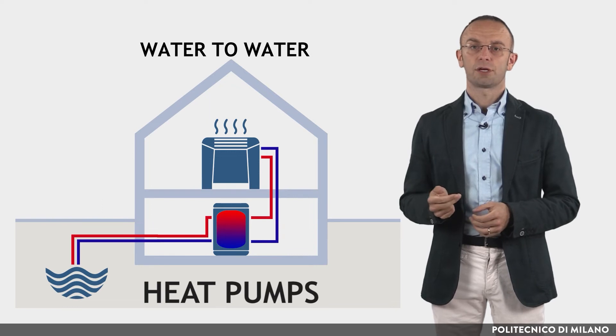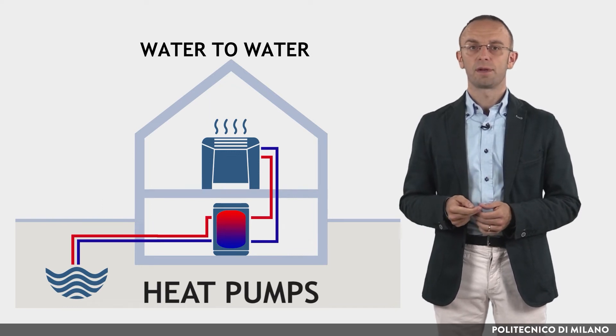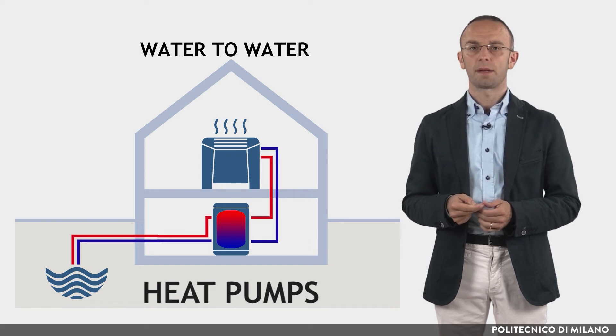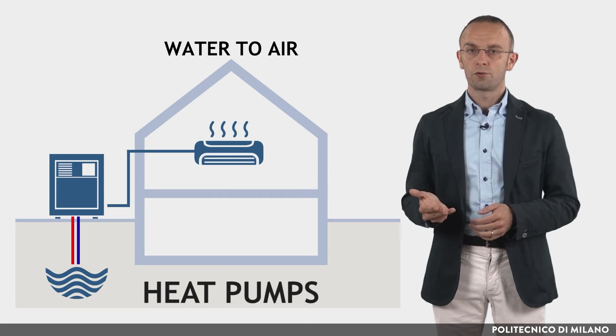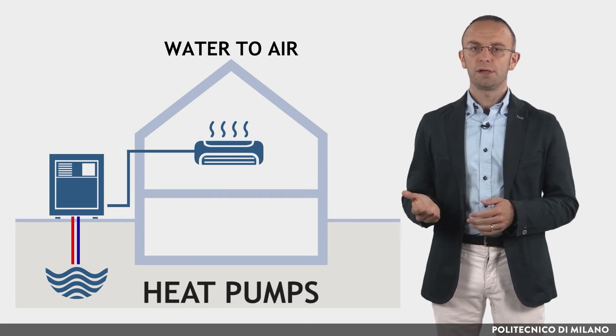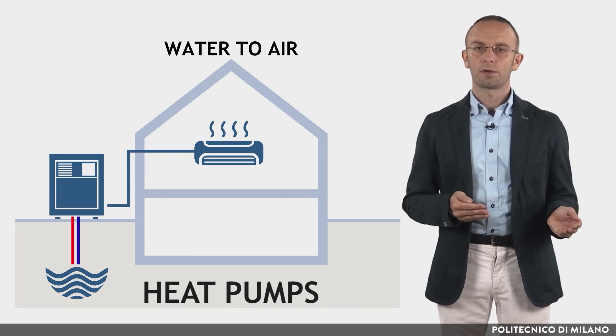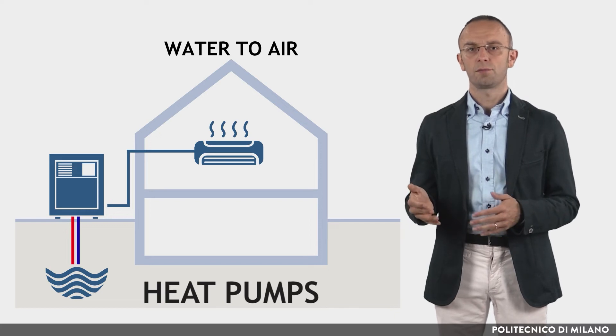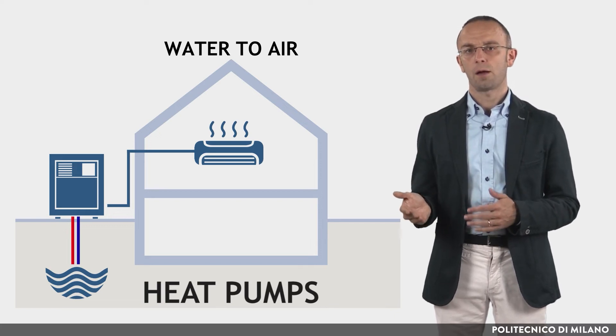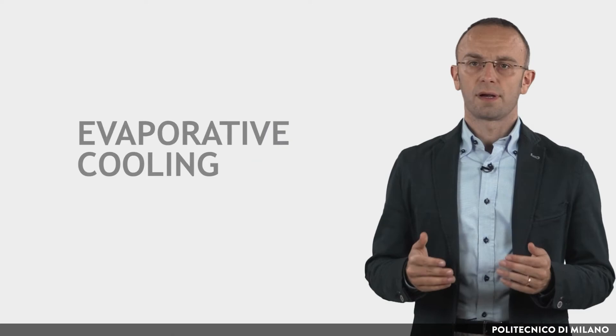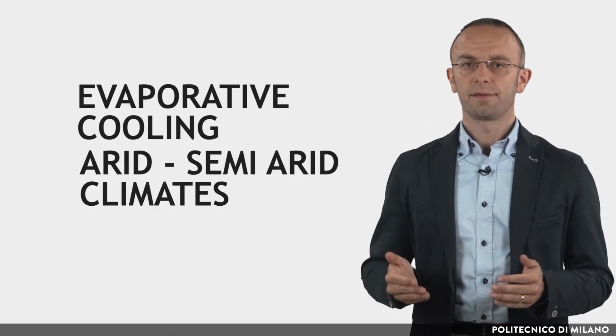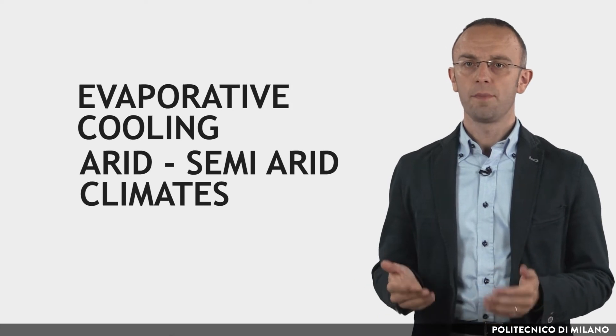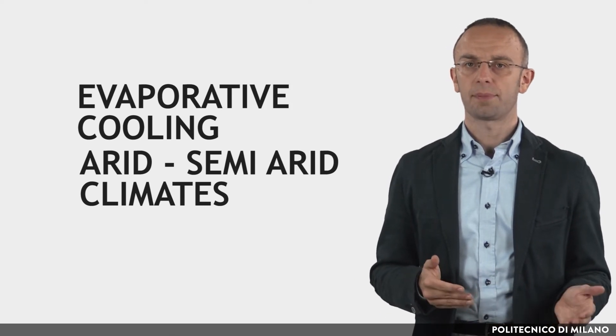Water-to-water: the refrigeration machine draws heat from the internal water circuit and transfers heat to the external environment by means of a water-cooled condenser. Water-to-air: the refrigeration machine draws heat from the internal water circuit and transfers heat to the external air by means of an air-cooled condenser. As regards evaporative cooling, it can be effective in hot, arid, and semi-arid climates, where humidity can be very low and temperature high.